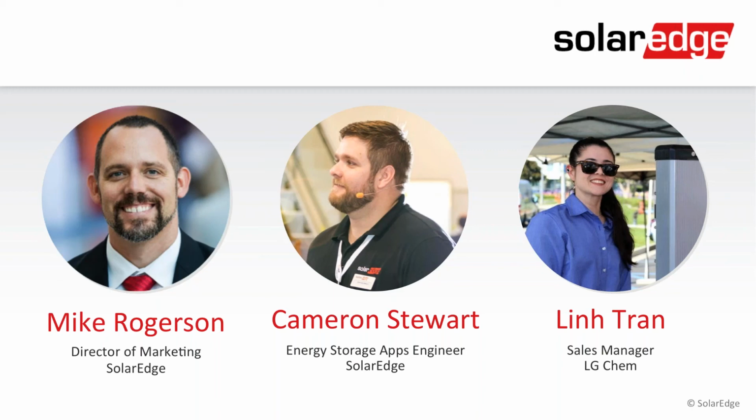And what some installers choose to do is they set a backup reserve. So they can say, I want to cycle 75% of the battery life, so 75% of the energy, and I want to reserve 25% of the energy. So if the grid goes out, I can run my battery on this 25%. I always have this little chunk that if the grid goes out, I can still power my loads.